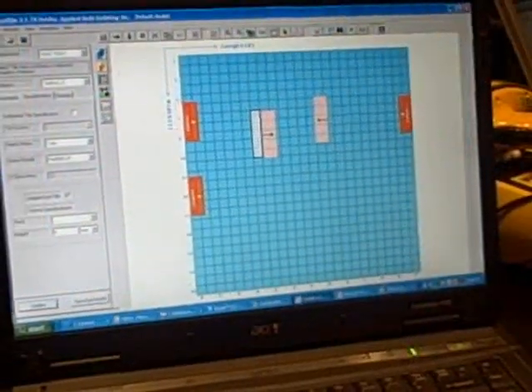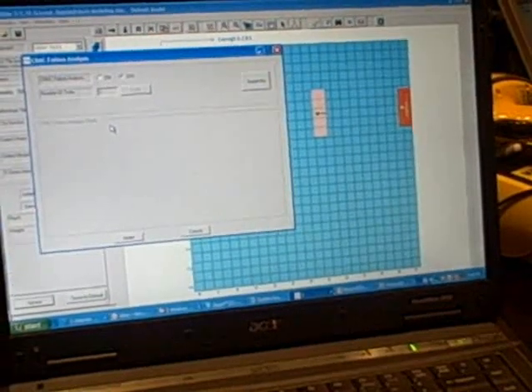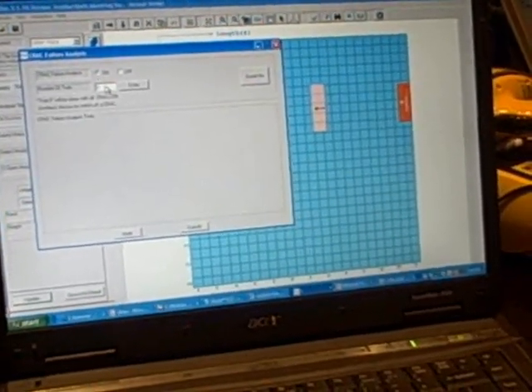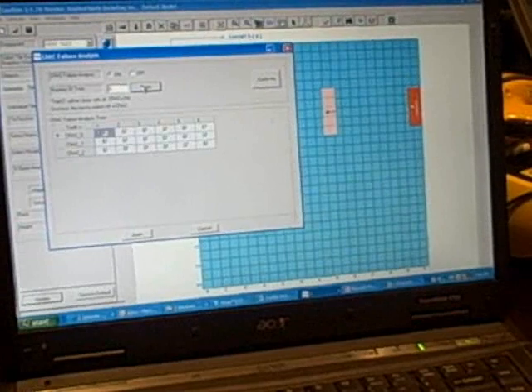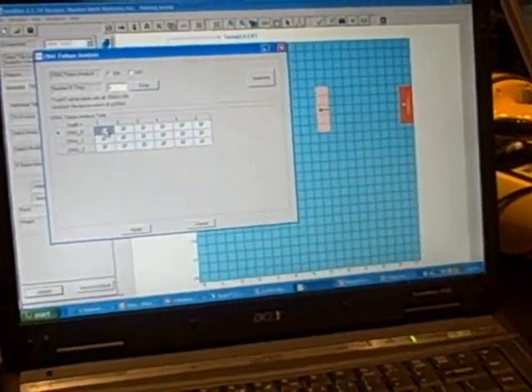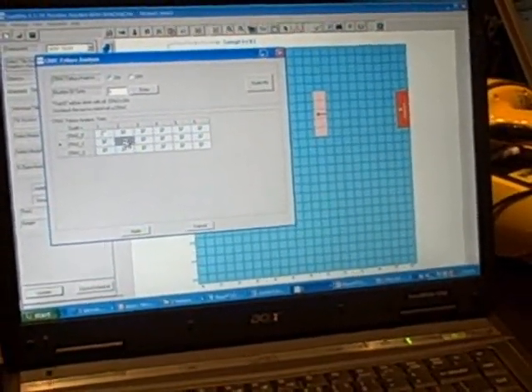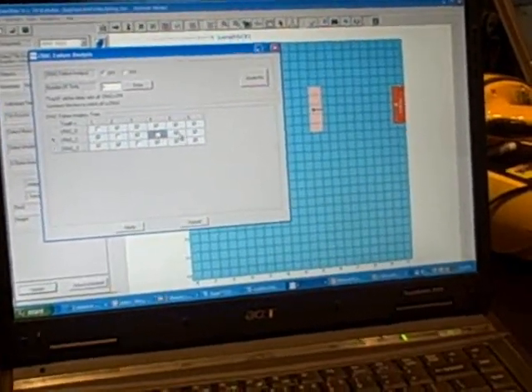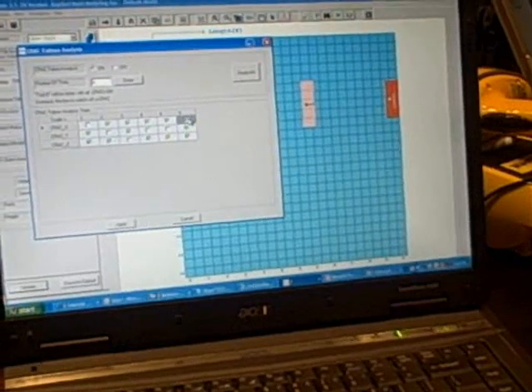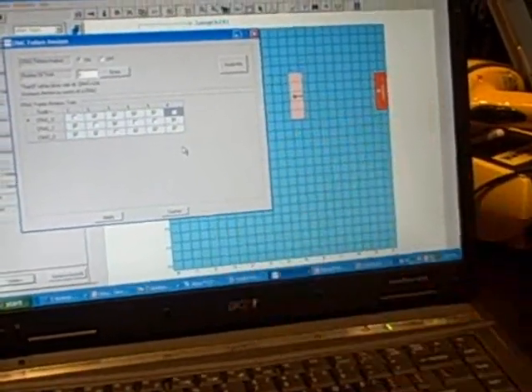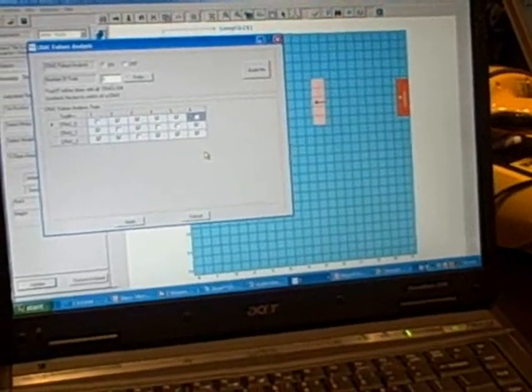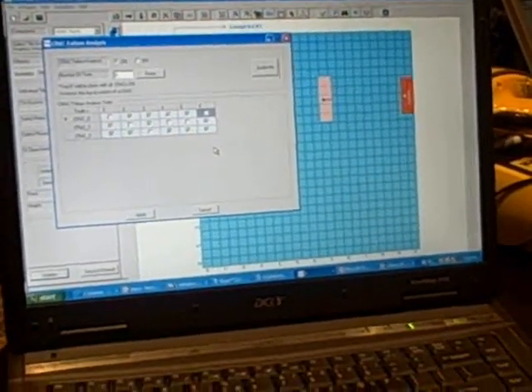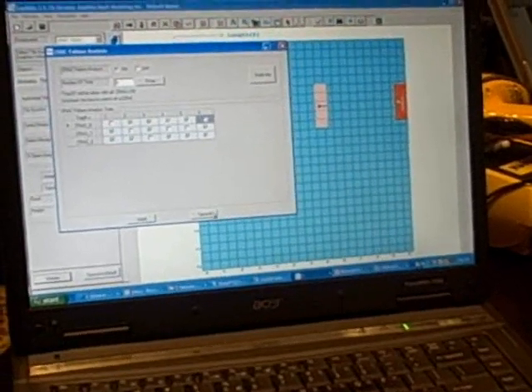One of the other features we've added in this one is the ability to do CRAC failure analysis. So I can turn on my CRAC failure analysis and enter into the number of runs I want to make, and this allows me to switch the CRACs off in a particular order and then submit these jobs all concurrently so that I can see the effect of what these jobs are going to have. I've picked six trials here. I've switched CRACs off for each one of these trials, and I can submit these all at once now, have them all run concurrently, come back with a unified report that shows you what the output looks like.